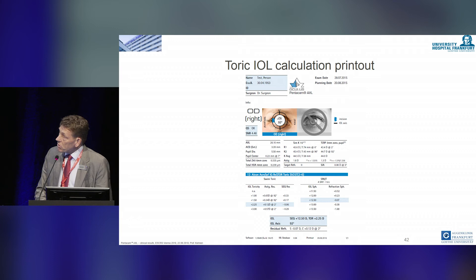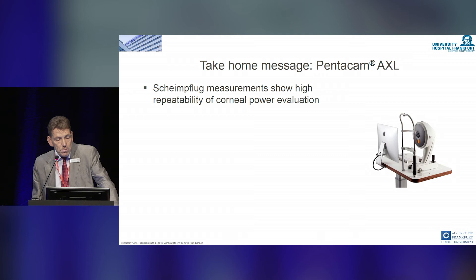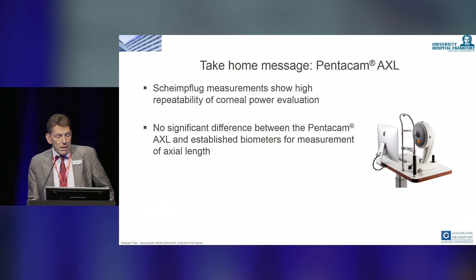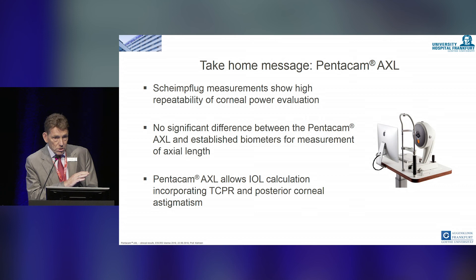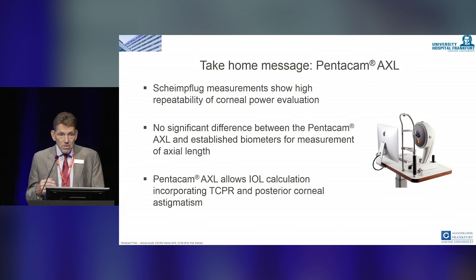Take-home message: Scheimpflug measurements show high repeatability of corneal power evaluation. There is no significant difference between the Pentacam AXL and established biometers for measurement of axial length. The Pentacam allows IOL calculation incorporating the posterior surface — the total corneal refractive power — and the posterior astigmatism. This is our next step: one device that does both measurements, which we usually have to combine. Thank you.